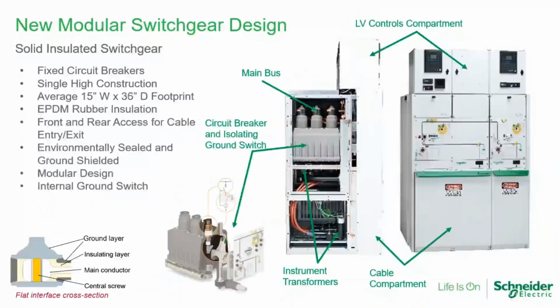Okay, so let's move on and look at now solid insulated switchgear. It looks very similar to the gas insulated switchgear in architectural style. Fixed mounted circuit breakers, single high design, but now we're shrinking down even smaller into the 15-inch wide range and 36-inch deep range. So we're getting even smaller than the gas insulated switchgear. This is a style that Schneider Electric makes called the PremSet, where we're using EPDM rubber as the insulator, but solid insulated switchgear designs can involve an epoxy, or an insulating rubber. There are various different styles of solid insulating material, and I'll talk a little bit more about that in a bit.